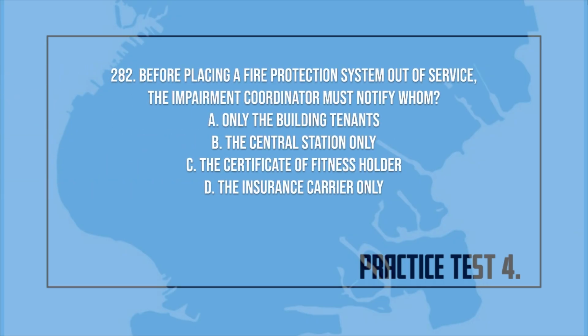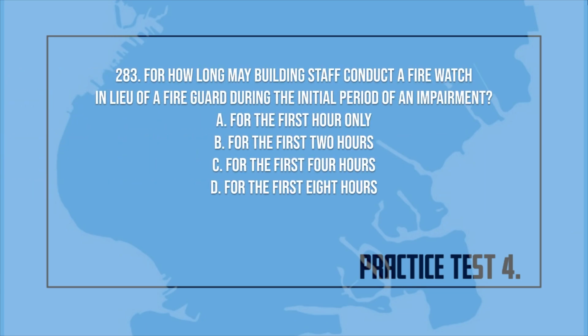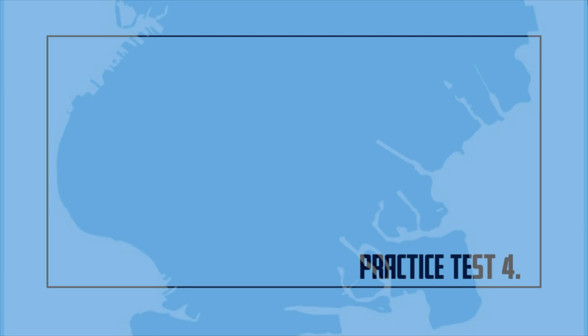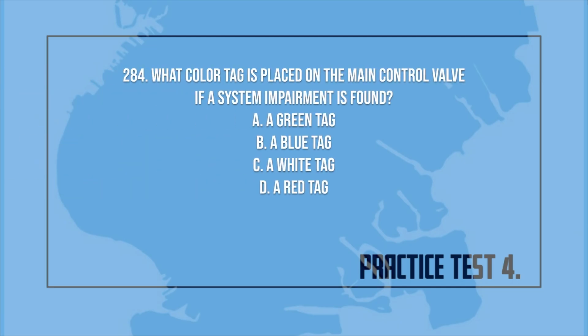282. Before placing a fire protection system out of service, the impairment coordinator must notify whom? A. Only the building tenants. B. The central station only. C. The certificate of fitness holder. D. The insurance carrier only. 283. For how long may building staff conduct a fire watch in lieu of a fire guard during the initial period of an impairment? A. For the first hour only. B. For the first 2 hours. C. For the first 4 hours. D. For the first 8 hours. 284. What color tag is placed on the main control valve if a system impairment is found? A. A green tag. B. A blue tag. C. A white tag. D. A red tag.